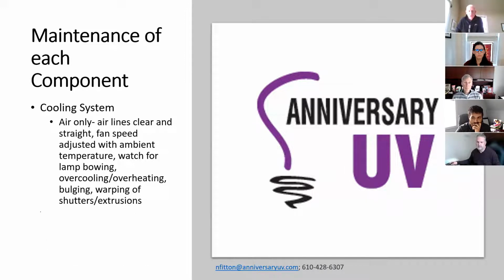All right, so then we talk about the cooling system. If it's air only, you have to keep the air lines clear and straight. I see situations where the airline is bent around another piece of equipment, going sideways. It's like the air conditioning system in your house. We want clean lines so the air can flow from end to end. The second thing to pay attention to is fan speed. In the summer, if it's hotter in the plant, we want to increase our fan speed. In the winter, we want to decrease it because it's colder in the plant. There is such a thing as overcooling, which I'll talk about later. We can get too cold or too hot, and we don't want that to happen.